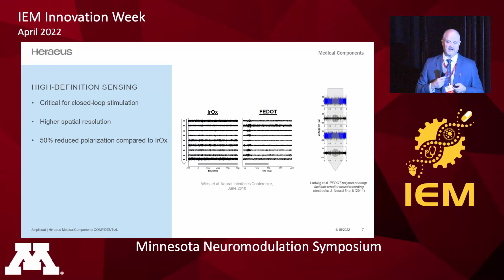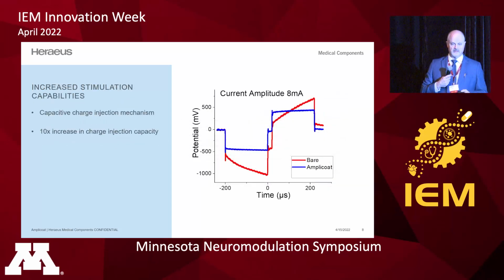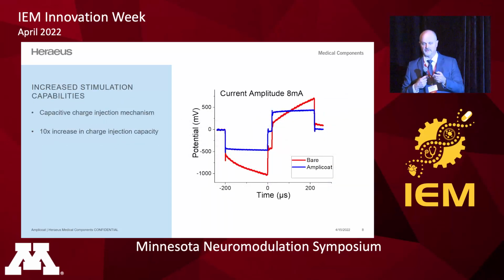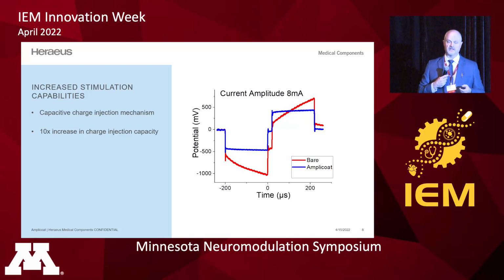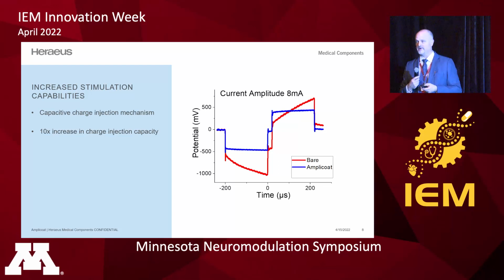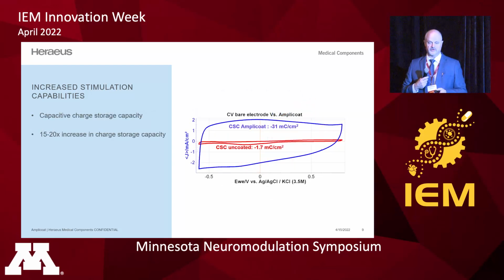One of the biggest benefits is high-definition sensing. So this is published literature showing the comparison between PEDOT, or Amplicoat, compared to iridium oxide, which is a standard coating that's used in CRM. And it's a 50% reduction in polarization. That's significant. Increased stimulation capabilities. You compare the two waveforms there, and it's a 10x increase in the charge injection capacity for a given pulse, which is significant. From a charge storage capacity standpoint, you can see about a 15 to 20x improvement for a given electrode.